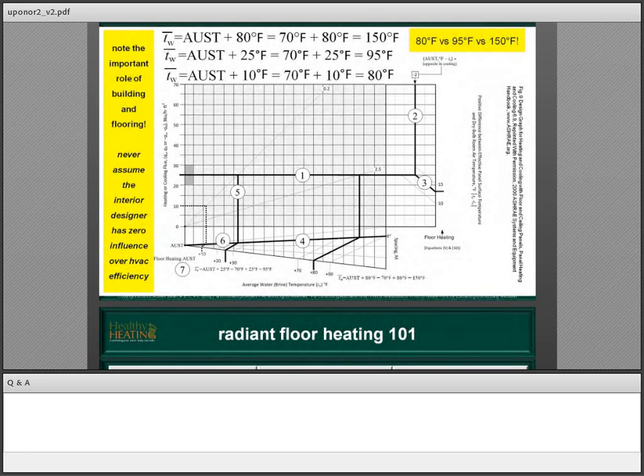So these are not trivial matters. When the radiant designer sits down with a builder, one of the objectives is to try to get the lowest temperature possible. How we do that is by working with the client to get the building load down, working with the interior designer to use, if you can, the lowest VOC materials, highly conductive, more than masonry type surfaces, and then using really tight tube spacing.